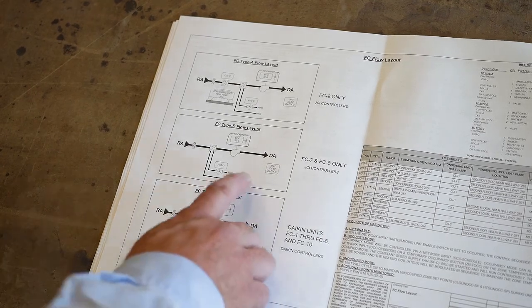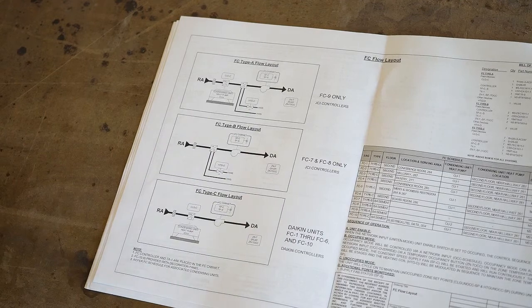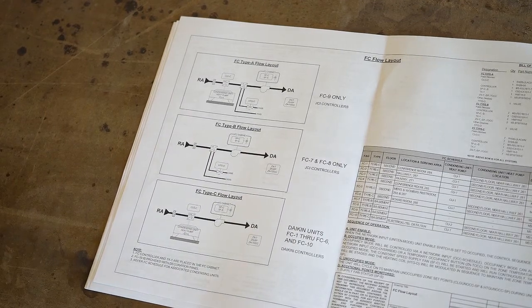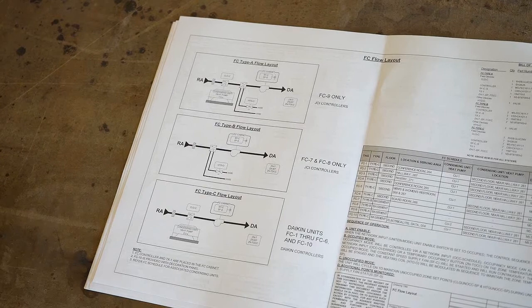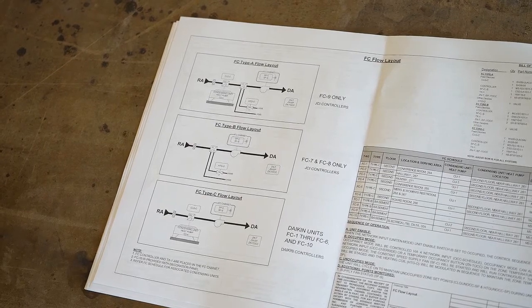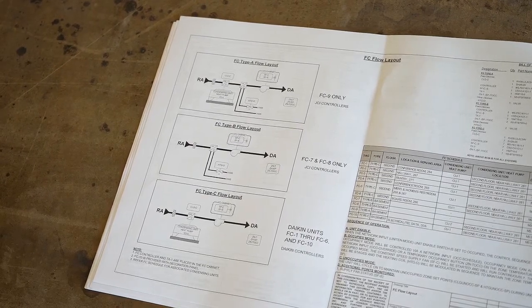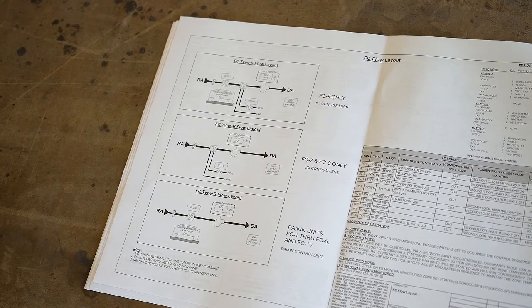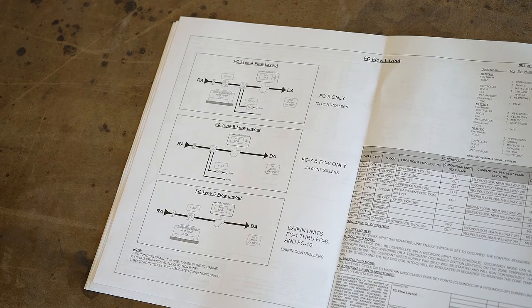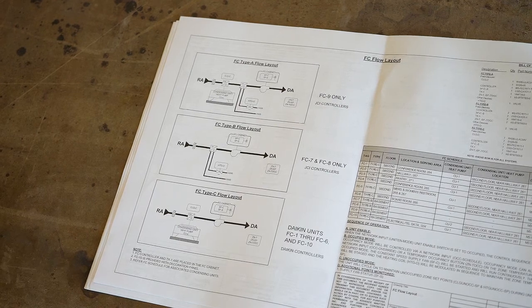Now the one in the main lobby area, there's 2 different sensors in there. We have one in the registration area that has the digital display on it, and it has a dial on there that can turn for a set point. Out inside the lobby on the other side of the wall, there's a stainless steel plate sensor. They actually wanted to get the lobby temperature to get a better average of what that lobby is, and then use the set point in behind the registration because they didn't want the public to play with it.